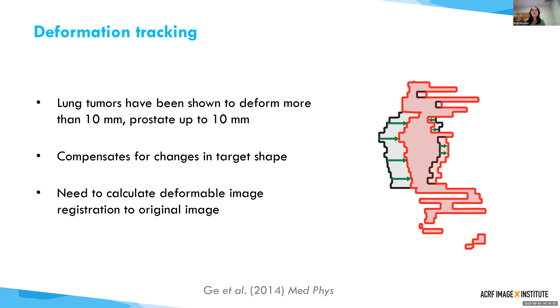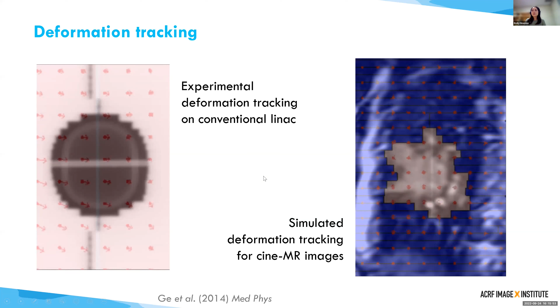So these are two examples of deformation MLC tracking being experimentally implemented. You can see if we have a deformation vector field of what the target is undergoing throughout the treatment, we can relay this information to the MLC controller to also deform the aperture shape to match that target accordingly. One of the main challenges in performing deformation tracking on a standard linear accelerator is actually being able to image this deformation and get that real-time anatomical information. So this can also be implemented on something like an MRI linac, where you're getting that high quality soft tissue imaging to allow us to get this anatomical information.